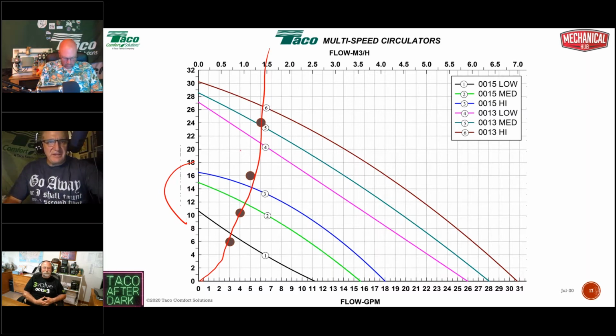So if it's speed 3, I'm really going to be working here at about 5 gallons a minute where I need 3. That's 66% more flow. My delta T's rarely, if ever, going to be in double digits. And I'm going to short cycle like crazy. Does that make sense to you?